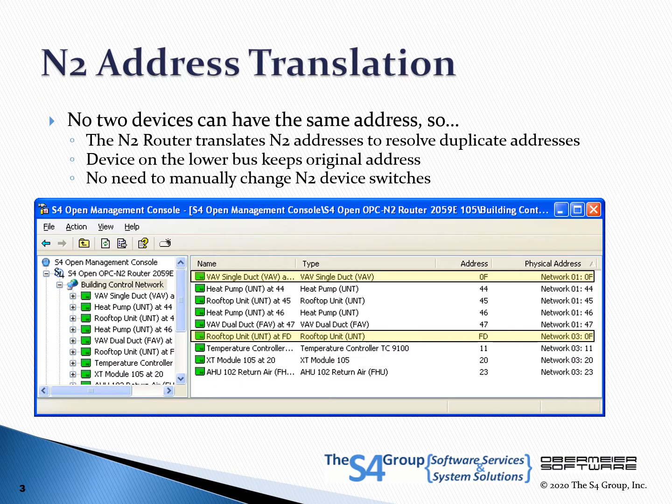In cases where you are supporting multiple N2 buses, the system automatically translates the N2 address as required to make sure all addresses published upstream are unique. Translation starts at the upper end of the address space and assigns the next available unused address.